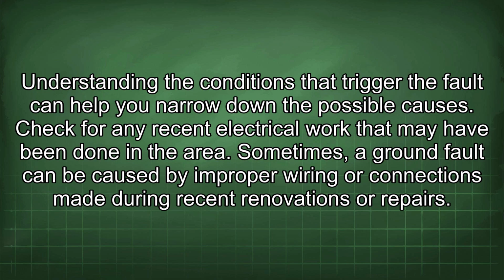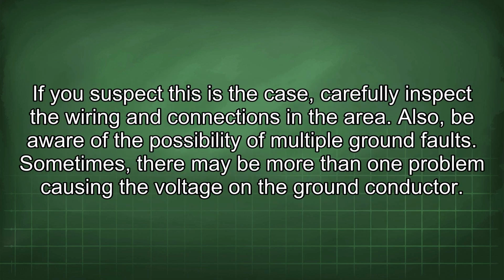Check for any recent electrical work that may have been done in the area. Sometimes a ground fault can be caused by improper wiring or connections made during recent renovations or repairs. If you suspect this is the case, carefully inspect the wiring and connections in the area. Also, be aware of the possibility of multiple ground faults. Sometimes there may be more than one problem causing the voltage on the ground conductor.